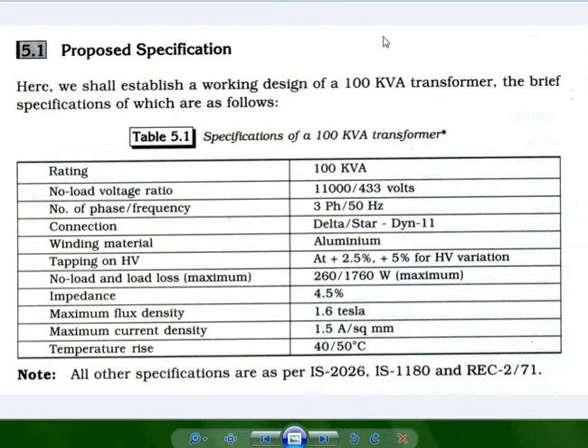You can see in the last row, temperature rise 40/50 degree centigrade. This 40/50, I told you at that time we will discuss it when we have a transformer tank to be designed. 40 over here is going to be the transformer outer side tank temperature, meaning if you look at the transformer's tank, it will be 40 degree centigrade.